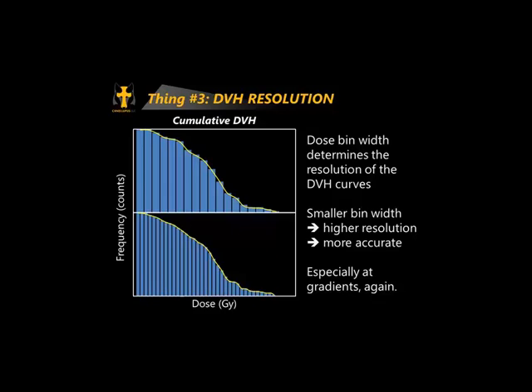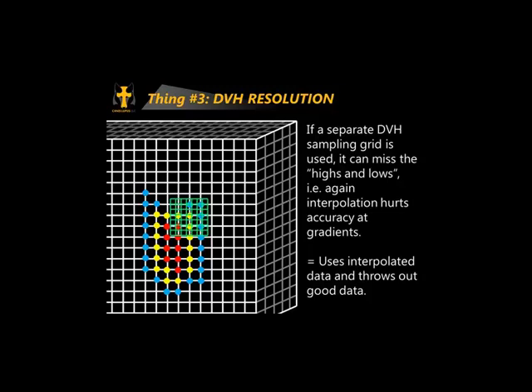There can be another problem besides bin width — at least in some planning systems. If a separate DVH sampling grid is used, what that means is there's already a three-dimensional dose grid, but some planning systems put an additional grid and count out interpolated dose values at a different resolution. You may completely step over actual dose points — and those dose points are the only ones we knew accurately. This uses interpolated data and throws out good data, just making more and more approximations.